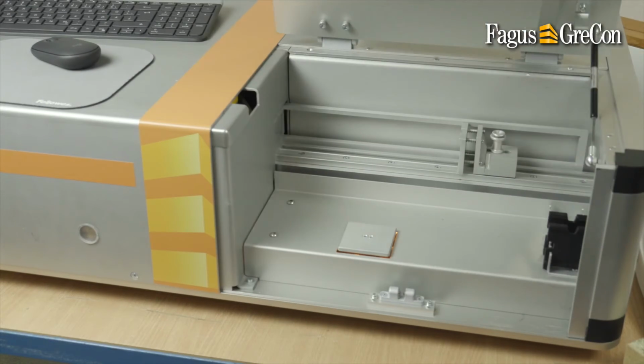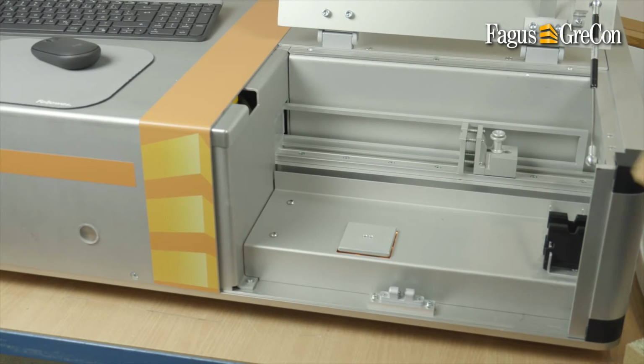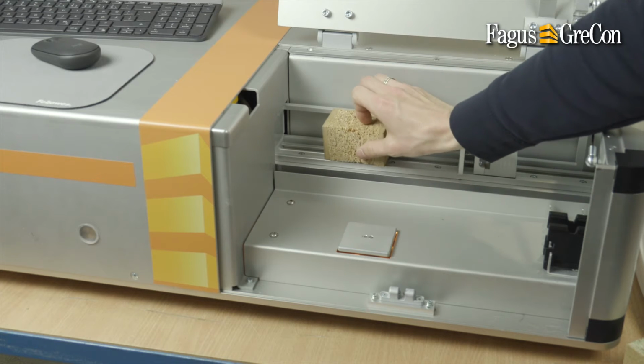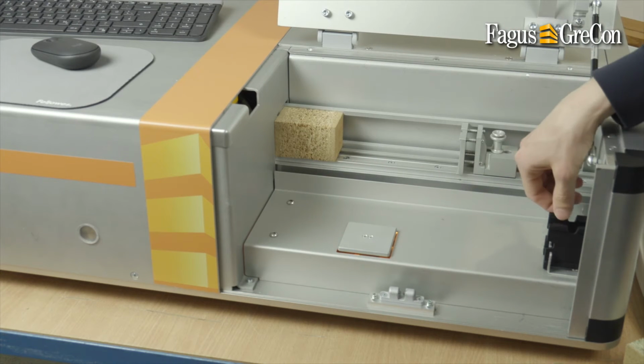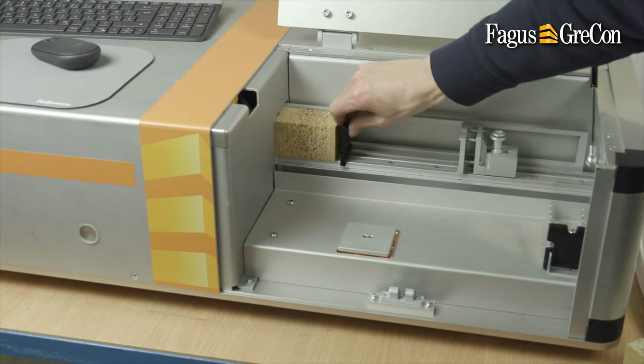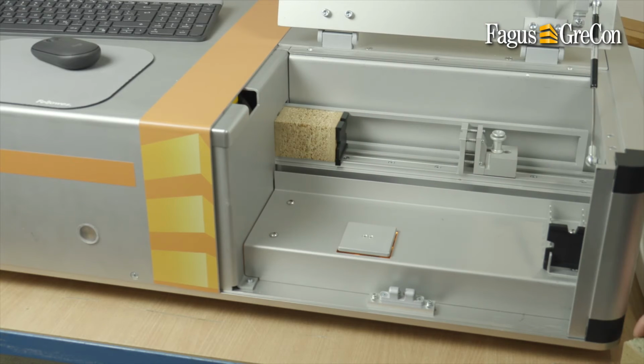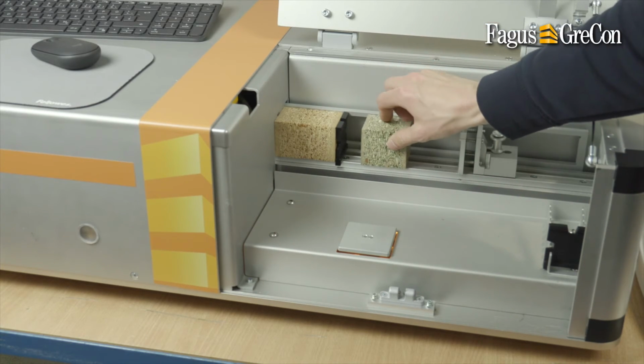The prepared samples are placed in the sample holder. Specimen thickness from 1 to 350 mm can be measured. Spacers are inserted between the individual specimens. For example, with a 20 mm sample, up to 11 samples can be measured in one pass.